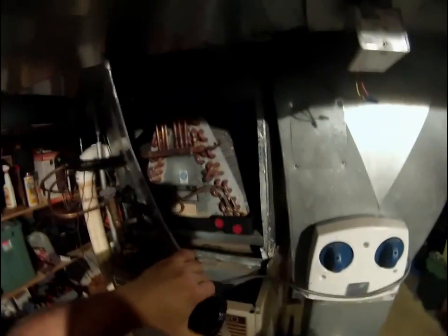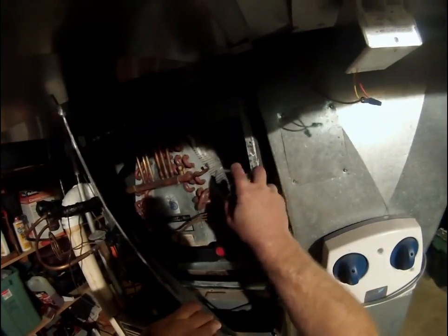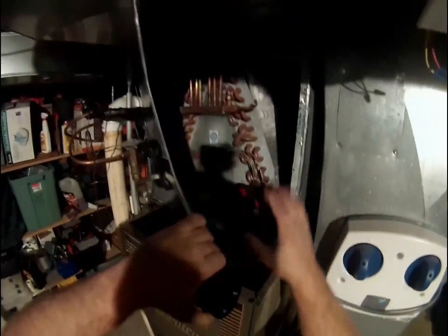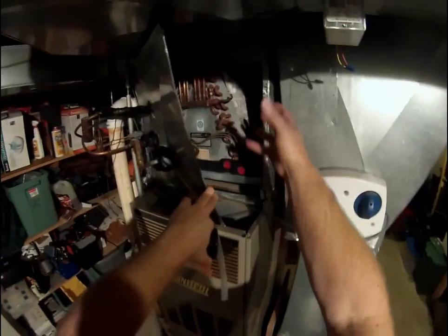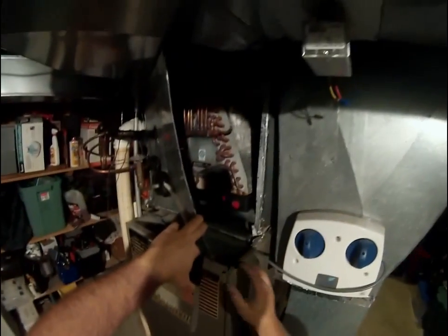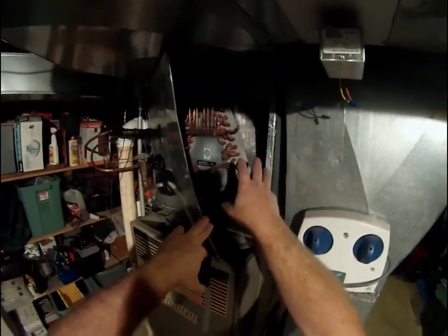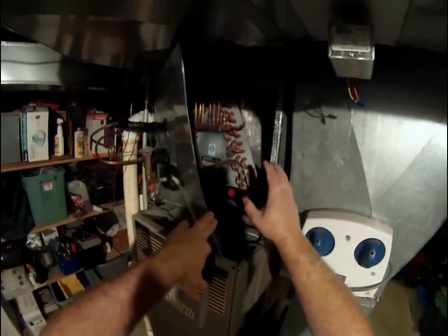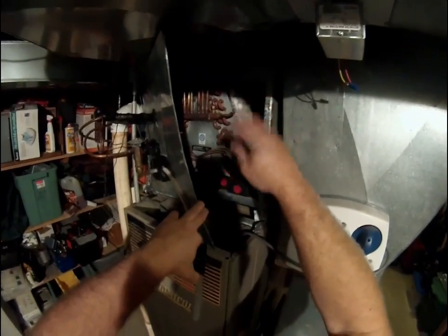And then we'll shake up this can of coil cleaner. And we spray that on there. And both sides, the opposite side will have the same thing. You can see how nice that foams up. And then when you're cleaning your outdoor coil, you can rinse it off with a hose. Obviously, I can't rinse it off with a hose here because it would then run water all over the unit. So our products are self-rinsing, meaning spray that all on there, get the heavy stuff, spray it all on there, and just let it rinse.